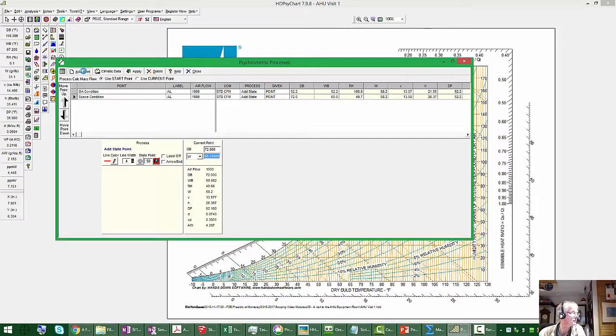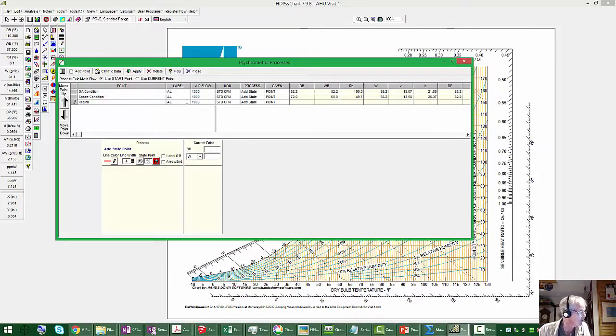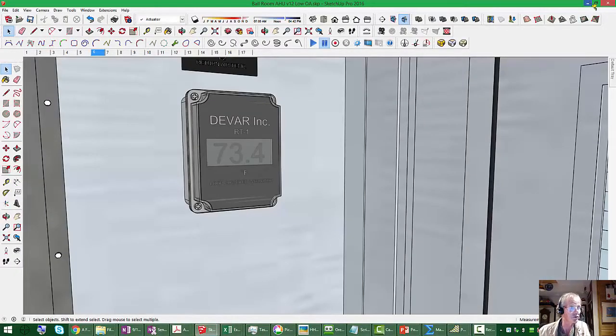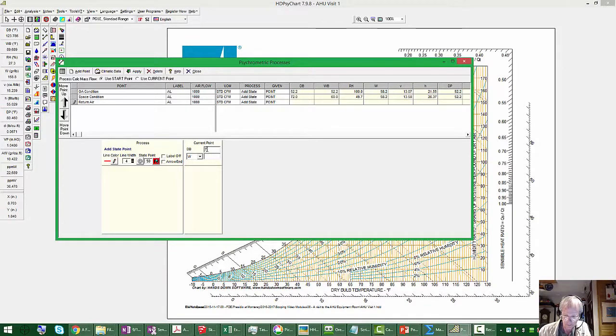So let's see here, go back to my psych chart. So I'm going to add another point. Call it return air. And it's unlikely that any moisture got added in the return air stream. So we're going to make that same assumption, that the specific humidity of the return air is the same as the specific humidity in the space, and plot that point on that basis. And so we're going to say the temperature in the return is the temperature we're reading here, 73.4. And the specific humidity, we're going to say again, is 58.2. And let's make that orange or something. And let's put the label below and to the right.